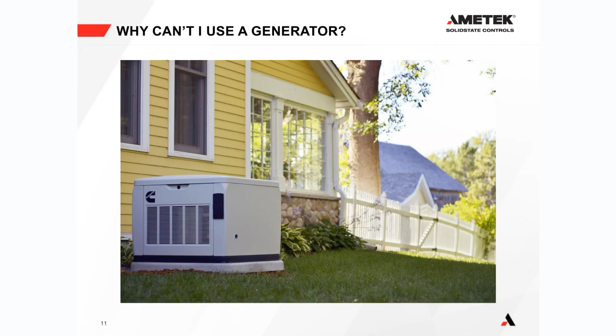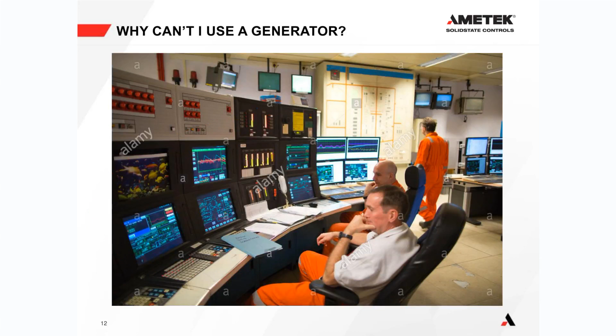But for other applications, like the DCS system - the distributed control system on an oil and gas platform or at a petrochemical refinery - the UPS powers all of these screens and controls. If all of those screens and controls lost power for 30 seconds, we could be in really big trouble, because there is no longer overview of the operation of the plant.